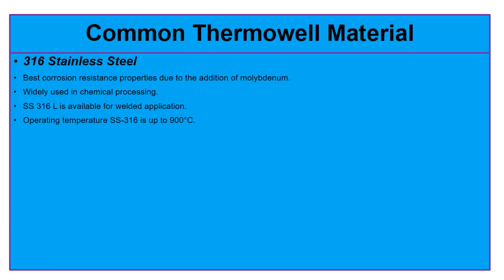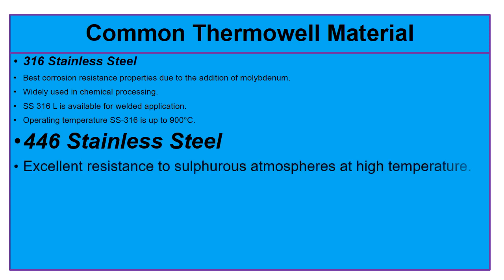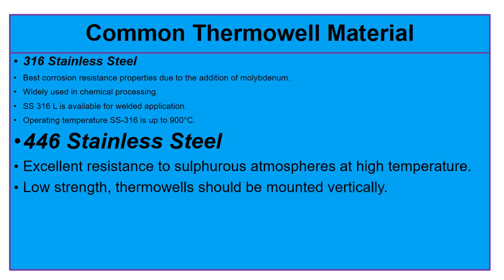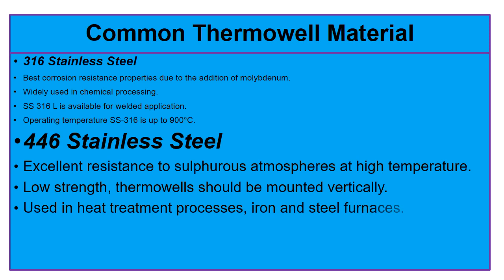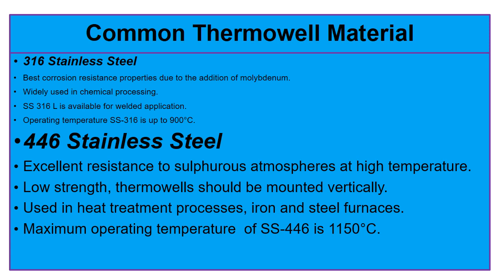Grade 446 stainless steel: SS 446 has excellent resistance to sulfurous atmospheres at high temperature. However, due to its low strength at high temperature, thermowells made from SS 446 should be mounted with the probe vertically. SS 446 is used in heat treatment processes and iron and steel furnaces. The maximum operating temperature of SS 446 is 1150 degrees centigrade.